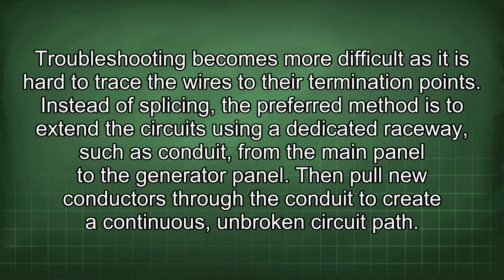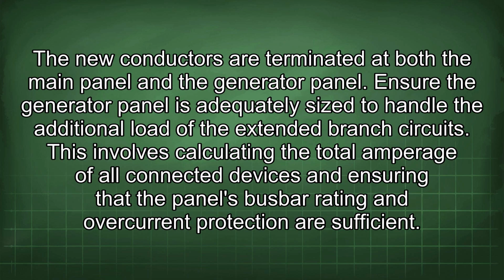Instead of splicing, the preferred method is to extend the circuit using a dedicated raceway, such as conduit, from the main panel to the generator panel. Then pull new conductors through the conduit to create a continuous, unbroken circuit path. The new conductors are terminated at both the main panel and the generator panel.